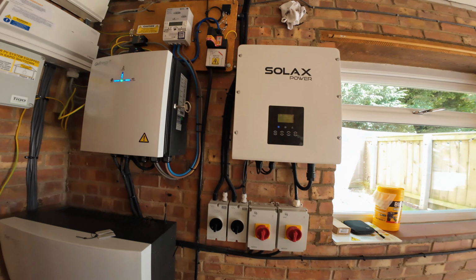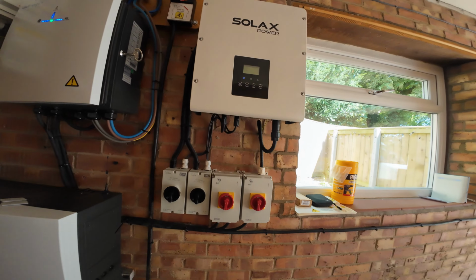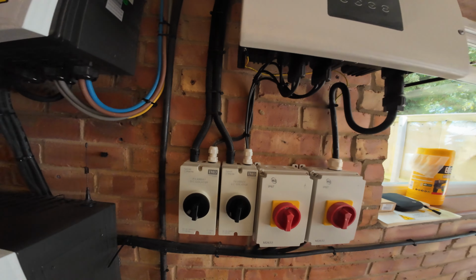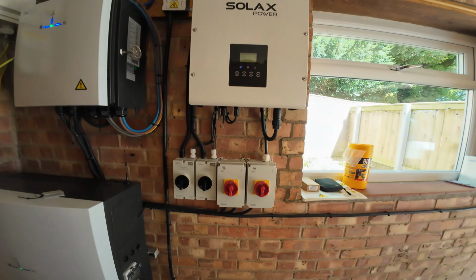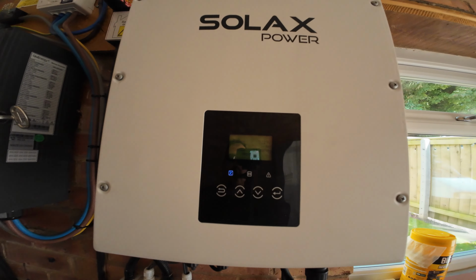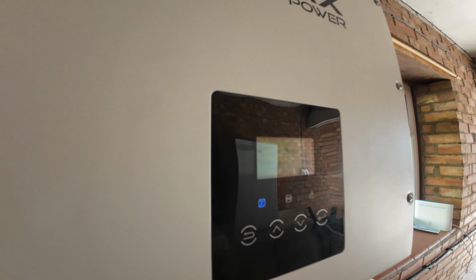The grid supply comes into the gateway, and then the house loads connect off through that. The inverter's sat here with the DC isolators, and again we've used some Flexicon on this. There was a lot of obstacles to work around - setting up a trunking system in and amongst the existing consumer unit just was a non-starter, so we've gone for this approach in this case.